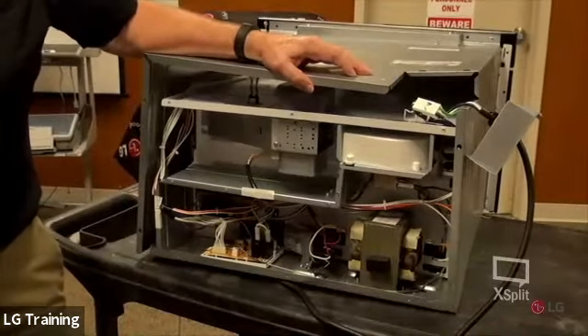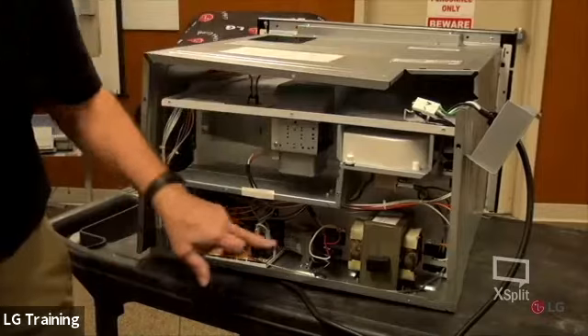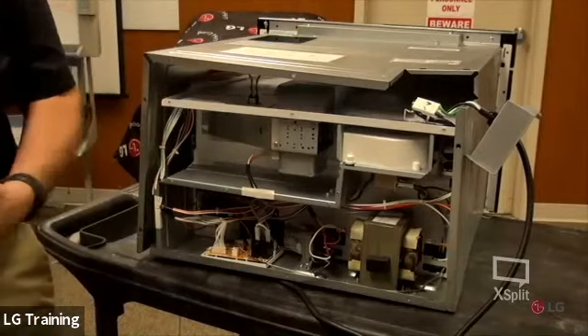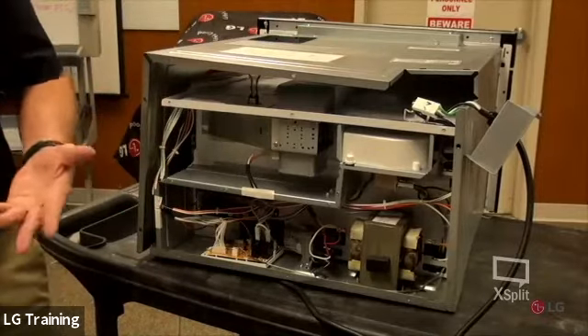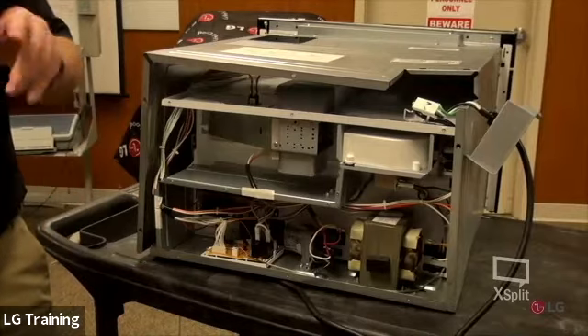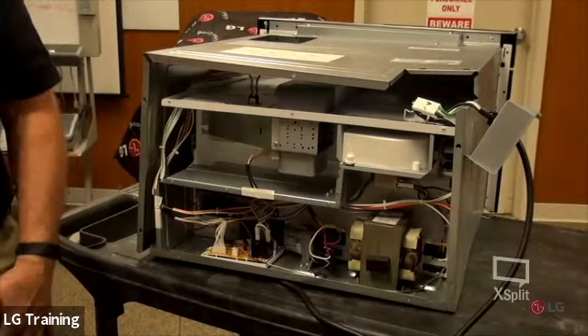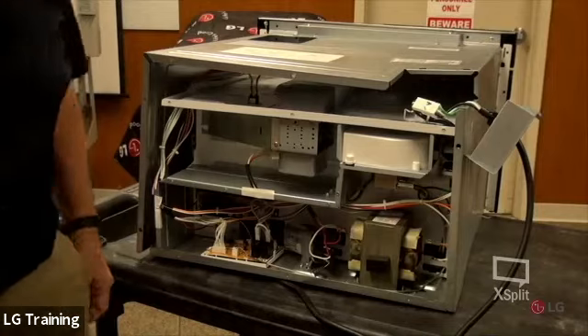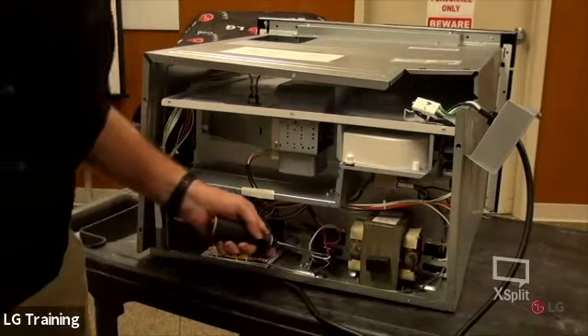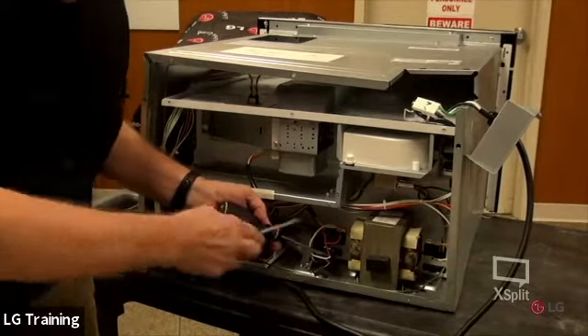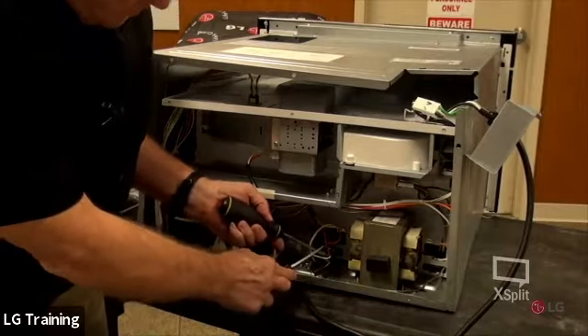What they did is they put a bleed off resistor inside this capacitor that's going to bleed it off, but we get complaints sometimes, and we're just assuming that resistor is okay. So always get in the habit of going across those terminals to make sure it's not holding a charge or anything.